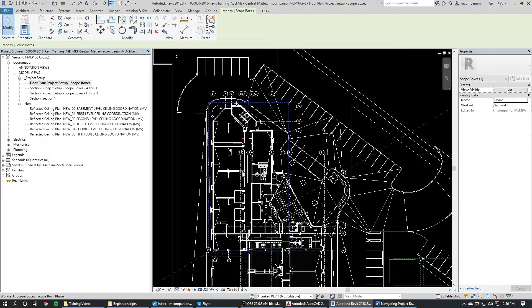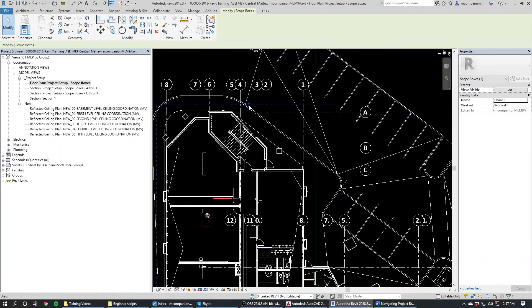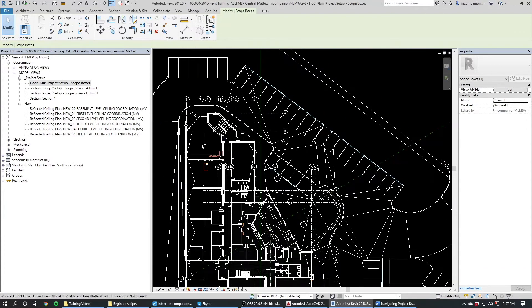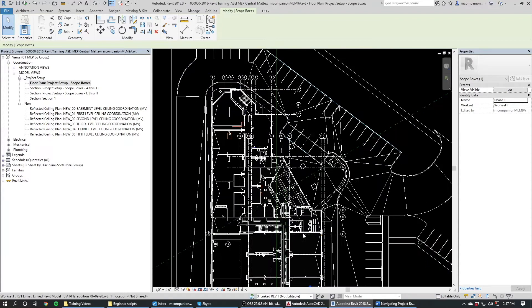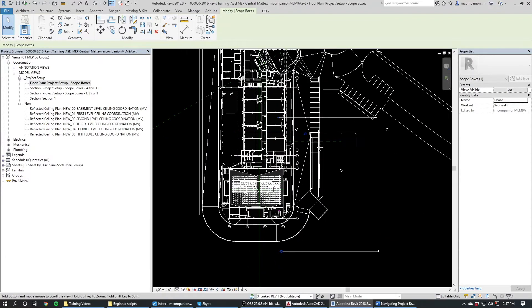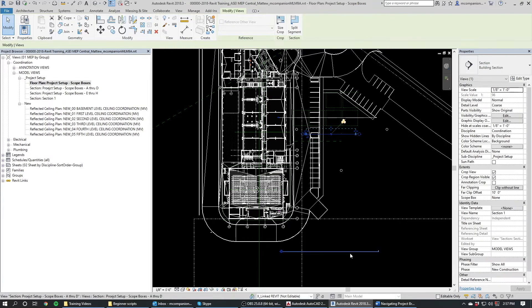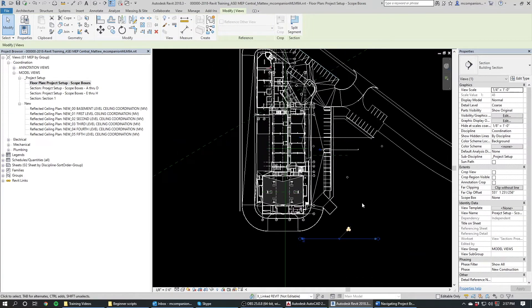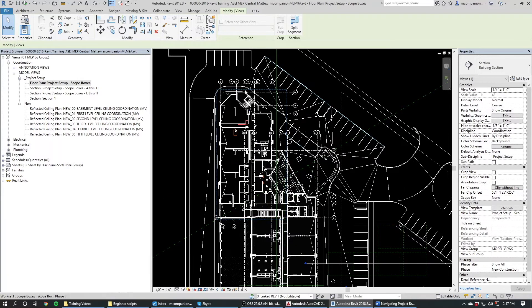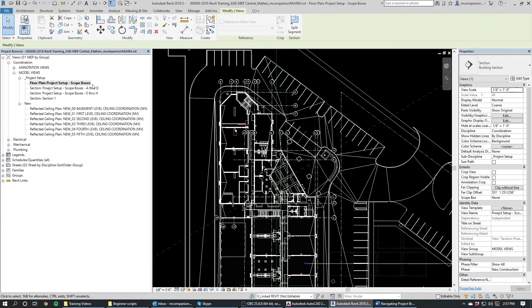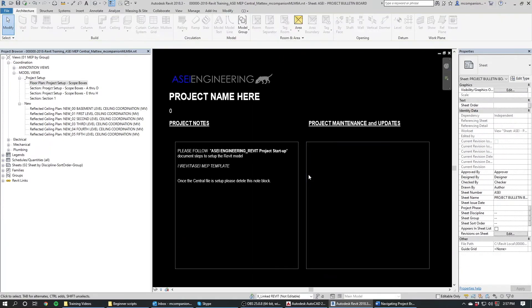And then that would cut all of this extra stuff out and just show you what's inside that box. So if that box needs to get bigger or smaller, depending on what your view needs to show, then you would come to this project setup view here in the coordination section, and you would change the scope box this way. So you click on it and just drag these little arrows up or down and it will change the view. Also in this project setup are these three sections, which are just section cuts through this view. These are used more in the setting up of your project. But for most of the time, you're just going to come in here, change your scope box a little bit and then just X right back out of this view.